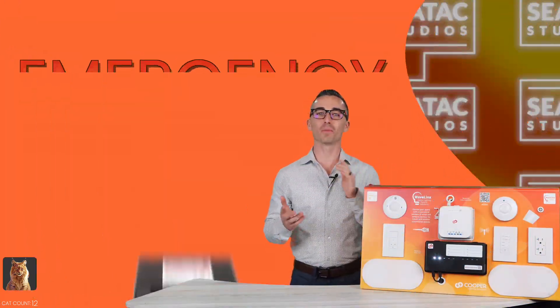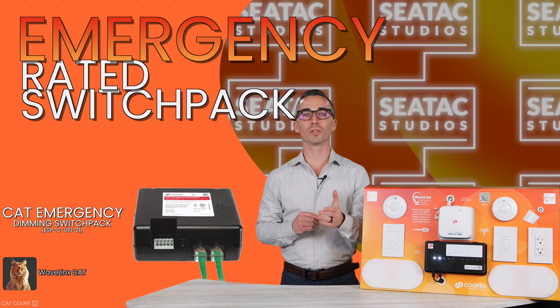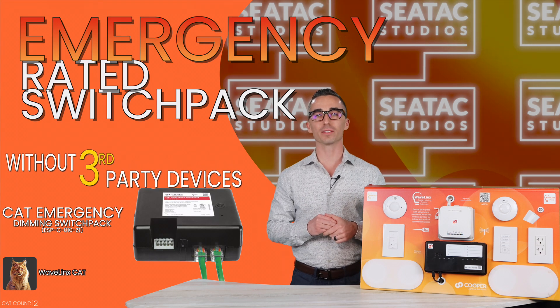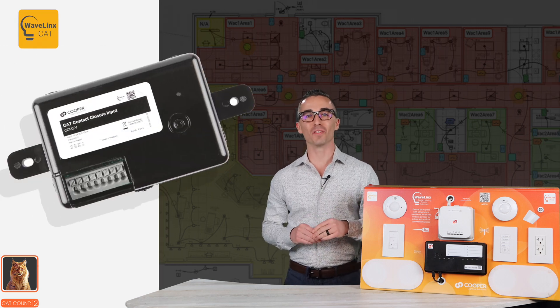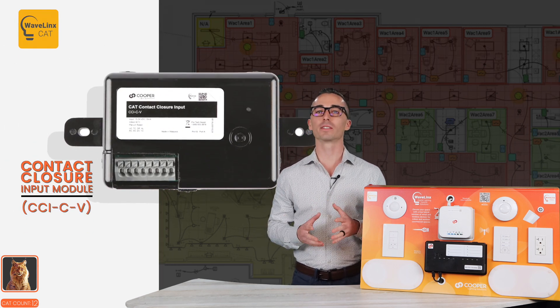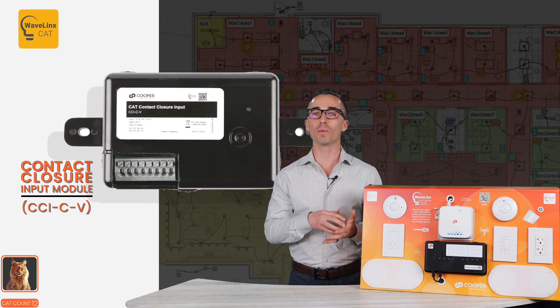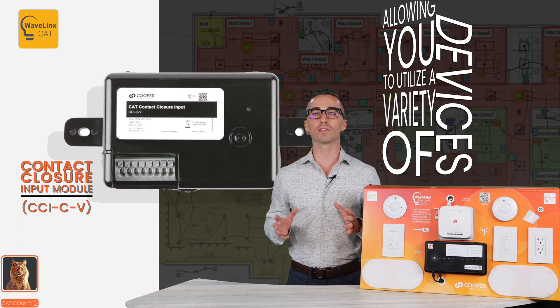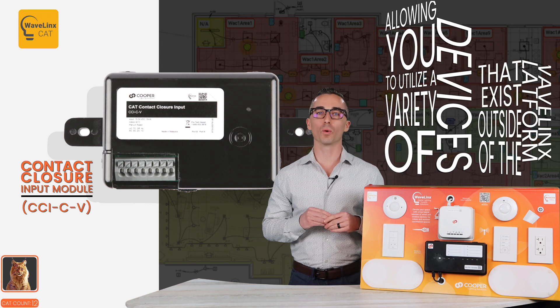The first one we'll talk about is the emergency rated switch pack, allowing you to meet UL924 requirements without having to add third-party devices. Another noteworthy device is the contact closure input module, which behaves as an input device that detects a maintained or momentary dry contact closure switch, allowing you to utilize a variety of devices that exist outside of the WaveLinx platform.